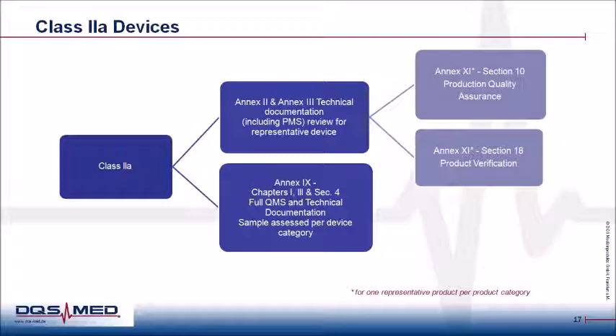prepare a declaration of conformity according to Article 90, and thereby the notified body will assess either the technical documentation of at least one representative product per product category covered by a basic UDIDI, that is Unique Device Identification Device Identifier, Annex 11 Part A Section 10, or the notified body carries out tests to confirm the conformity of the devices according to Annex 11 Part B Section 18.